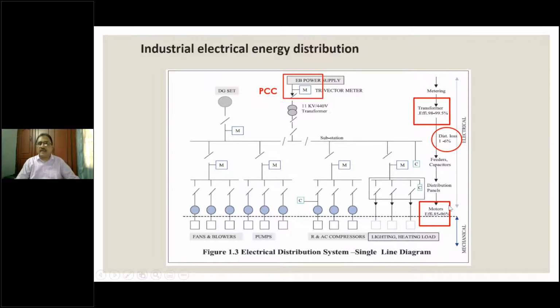Similarly, if you look at the end-use products, motors account for almost 70% or more in some industries, and efficiency could vary between 85 and 96%. This variation is primarily because of the size of the motors. All lower-size motors are very inefficient. All medium and large-size motors have sufficiently higher efficiency of 90 to 96%. But motors below 10 horsepower or 7.5 kilowatt are 85% or less.